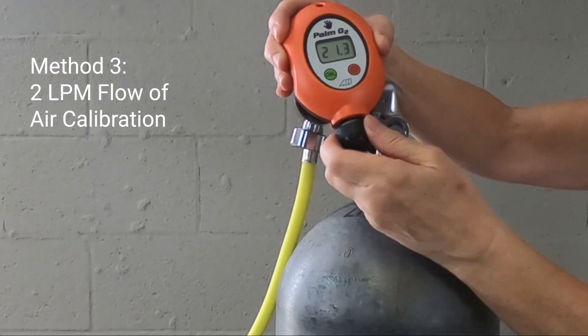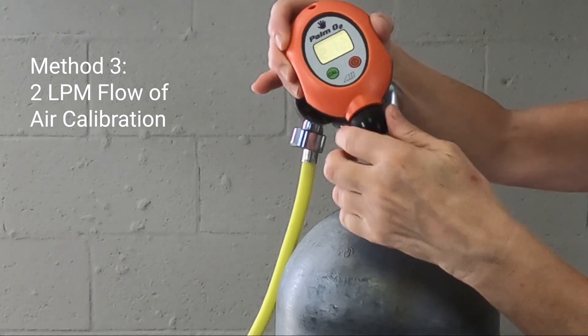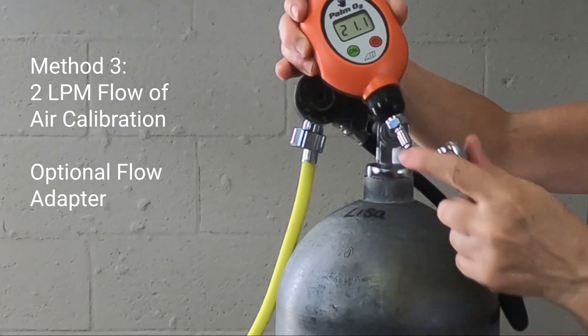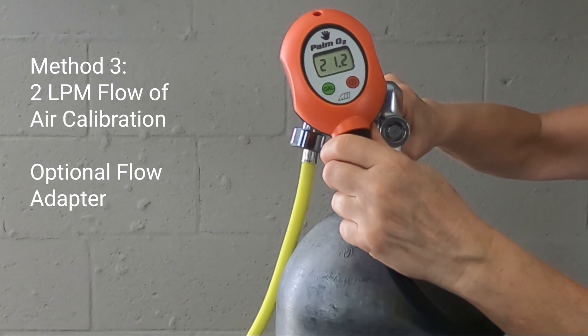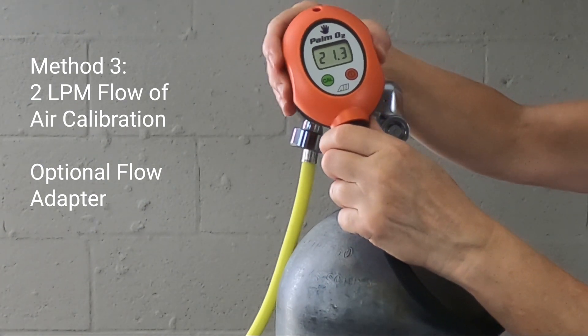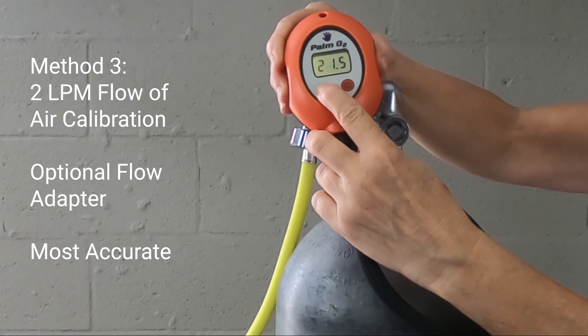Finally, the third method is calibration with a precise 2 liter per minute flow of air using the optional flow adapter. The flow adapter provides the most consistent and accurate calibration.